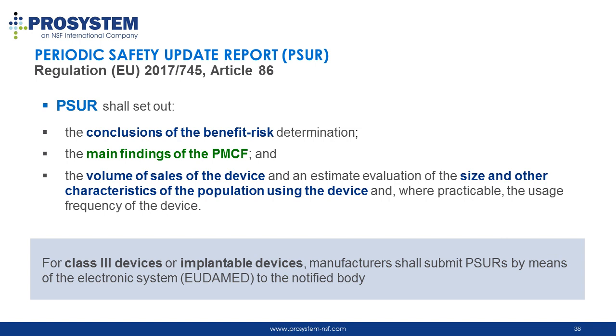The PSUR should be made available to the notified body, and in the case of Class 3 and implantable devices, it should be submitted by the electronic system called EUDAMED.